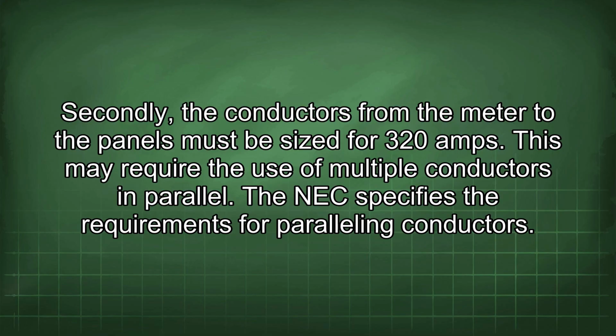Secondly, the conductors from the meter to the panels must be sized for 320 amps. This may require the use of multiple conductors in parallel. The NEC specifies the requirements for paralleling conductors.